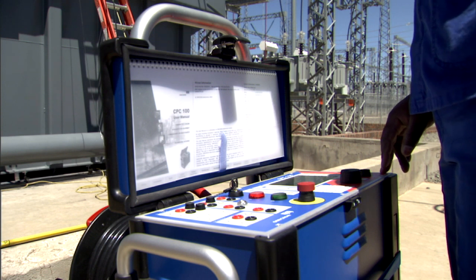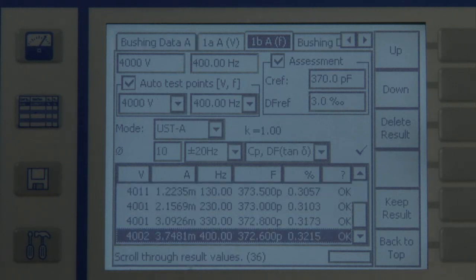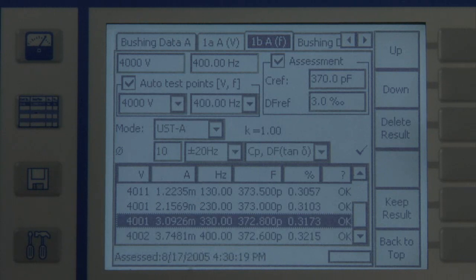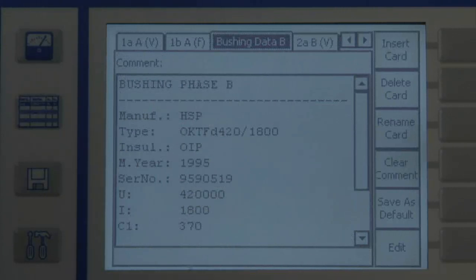The results of both the voltage-dependent measurement of the dissipation factor or the power factor are displayed. This is then repeated for the bushings of phase B, phase C and the neutral conductor.